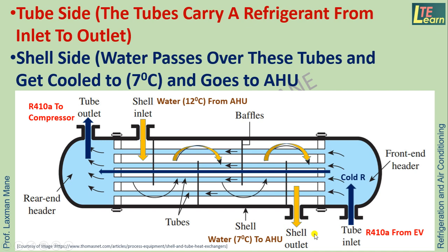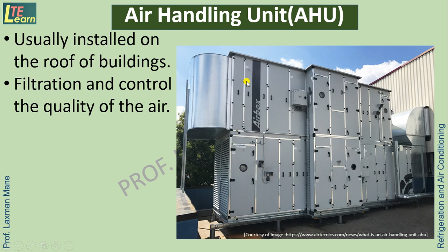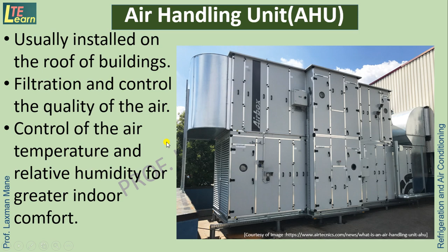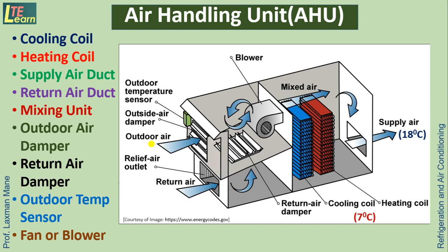The air handling unit is usually installed on the roof of buildings. It plays a major role in filtration and control of the quality of the air, and control of the temperature and relative humidity for greater indoor comfort. The air handling unit mainly consists of a cooling coil, heating coil, supply air duct, return air duct, mixing unit, outdoor air damper, return air damper, outdoor temperature sensor, and fan or blower. In the air handling unit, the temperature of the conditioned space is maintained at 24 degrees Celsius.